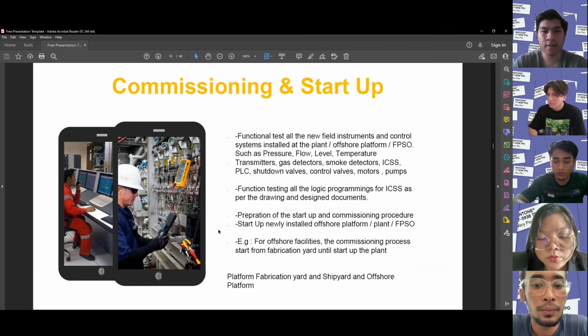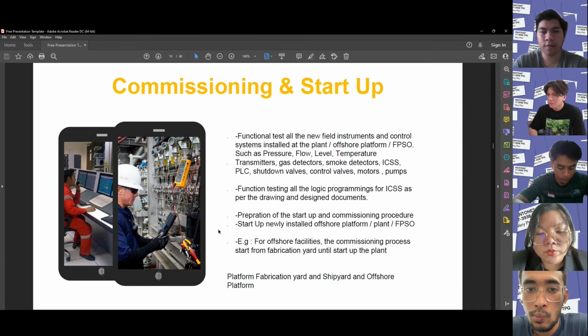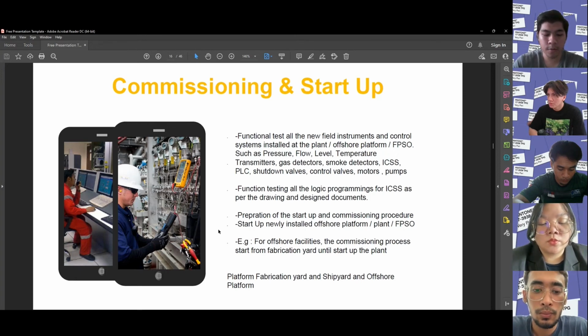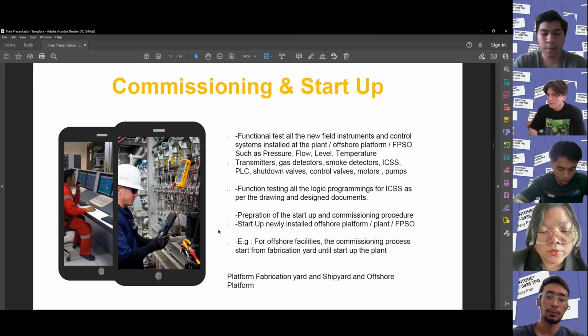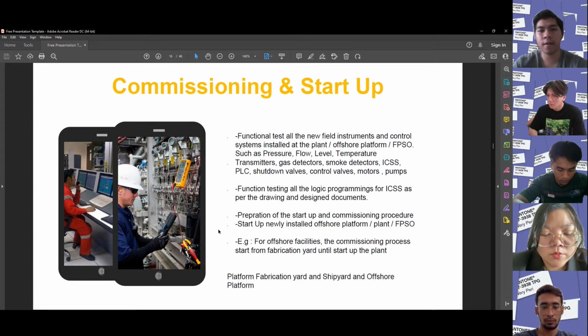So the next one is commissioning and startup, which is quite important for any project. Usually in commissioning and startup, we test the function of all the new field instruments and the control system at the plant. You control the PLC, the shutdown valve, the temperature transmitter, and the flow and level of the water flow maybe. And we have to test the logic programming of the ICSS as per drawing and design document.